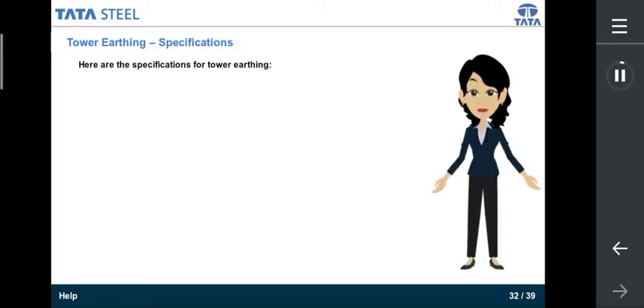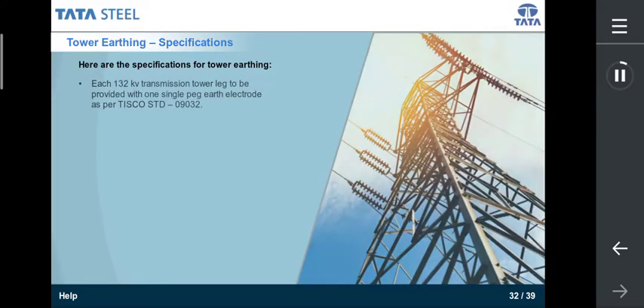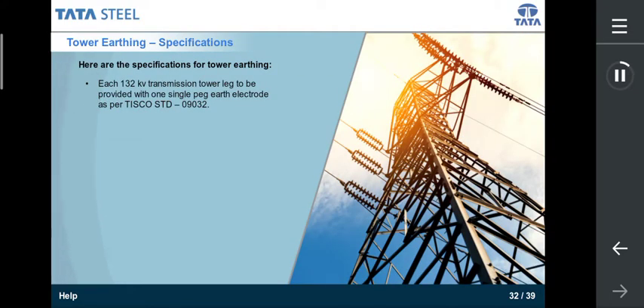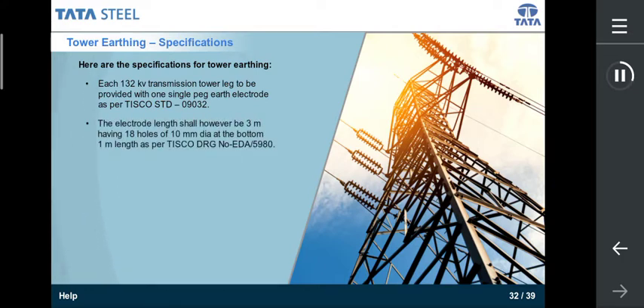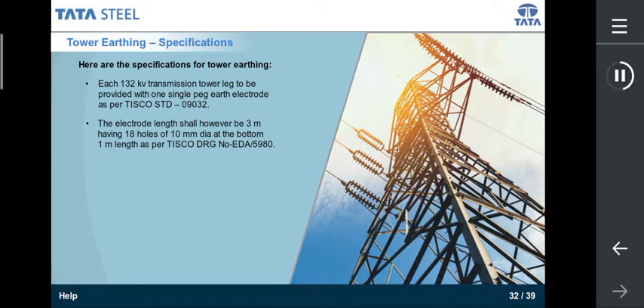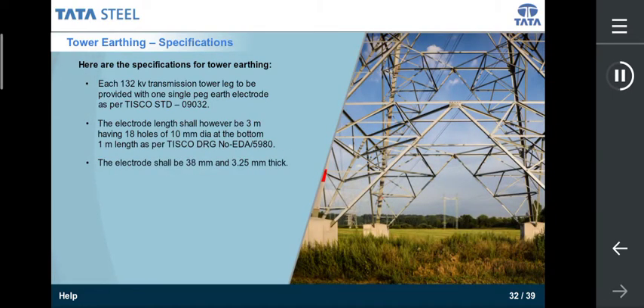Let us now look at the specifications prescribed for tower earthing. Each 132 kV transmission tower leg is to be provided with one single peg earth electrode as per TISCO standard 09032. The electrode length shall however be 3 meter with 18 holes of 10 mm diameter at the bottom 1 meter, as per TISCO DRG number EDA by 5980. The electrode ID shall be 38 mm and 3.25 mm thick.